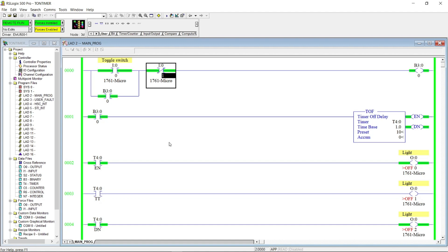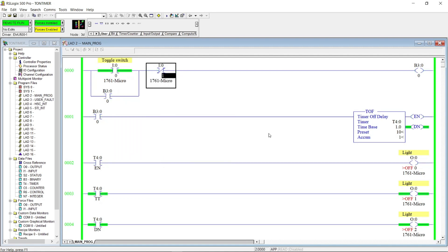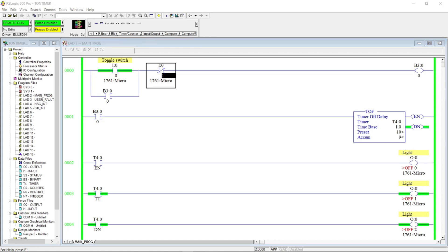Now let's go on to Timer Off Delay, or TOF. This type of timer is the opposite of the On Delay timer — this one is delay turning off. After the input sees a target, an output will turn on. And when the input no longer sees the target, it holds the output for a certain number of seconds before it turns off. As you can see, when the accumulated value reaches 10 seconds, outputs O:0/1 and O:0/2 will turn off.